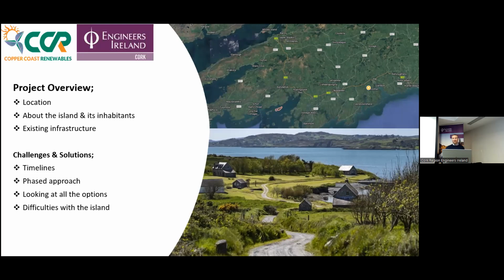One of the other things we looked at is that the island is largely uninhabited - there are two full-time inhabitants, plus workers in and out nearly every day. The main load is the heat pumps running the underfloor heating, keeping the homes warm and keeping the damp out. So the load during the day across the 7 sites is about 7 kilowatts, but at night time, or just before morning and at night, you're up over 10 kilowatts. So the load is actually steady during the day.